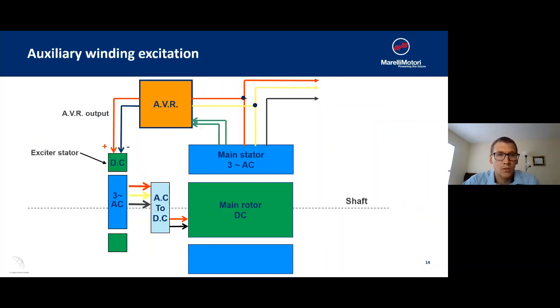If we look here we're going to look at the AC and DC current and how they flow through this system. The AVR puts DC current into the exciter stator. It induces three phase AC current in the exciter rotor which is then rectified to DC current to power the main rotor. And that DC current is what's going to induce the current in the main stator.